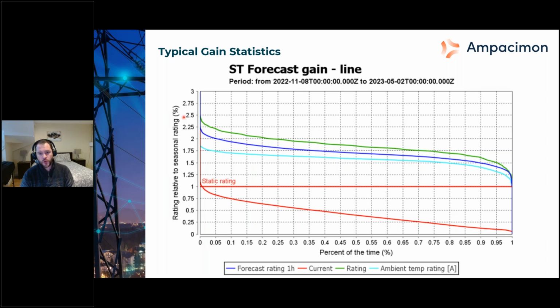So when you see 2.5, that's actually 150% gain on the static rating in this particular example. Now, I've chosen a really great line here. This line is in the Nordics, so it's cold, it's windy, and the static rating was quite conservative. So this is a really great example.